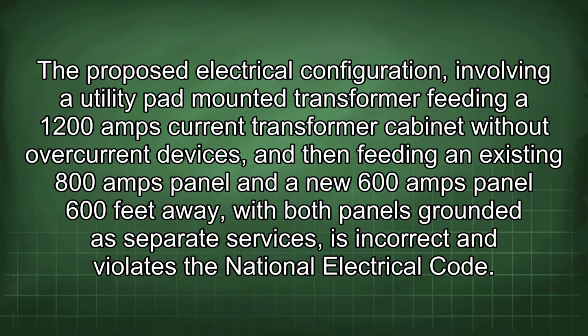The proposed electrical configuration involving a utility pad-mounted transformer feeding a 1200 amps current transformer cabinet without overcurrent devices, and then feeding an existing 800 amps panel and a new 600 amps panel 600 feet away, with both panels grounded as separate services, is incorrect and violates the National Electrical Code.